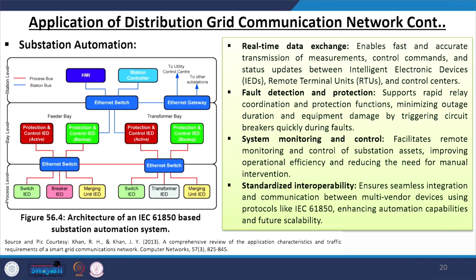Then you have substation automation, obviously that is needed, because in the substation you have multiple relays, you have isolators, you have other devices which need to be controlled or communicated properly. So, that is done by real time data exchange, which enables fast and accurate transmission of the measurements, control commands and status updates between the intelligent electronic devices and RTUs.